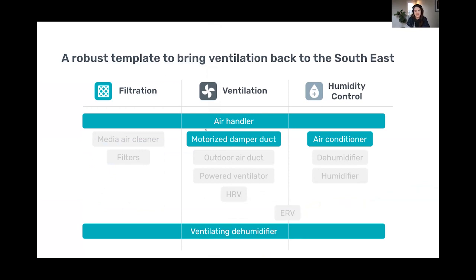Yeah, so we're just being a bit more explicit here again. There's the ventilating dehu, which we know solves issues across all pillars. In an ideal situation, it's also running alongside an air handler so that we get that mixing, so that we have the positive effects of the AC. But then that motorized damper duct, the beauty of an integrated system is we can open and close the duct when needed. So integrating with outdoor AQI, for example, this was a question that came up in the chat earlier. If there are issues that cause the AQI to rise, if we have control over the damper, we can make sure that we're closing that off if outdoor air starts becoming worse than the indoor air.